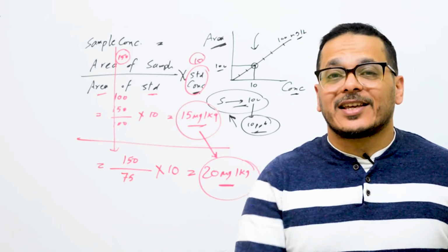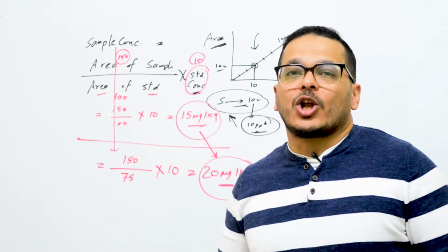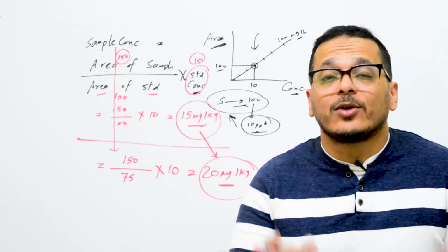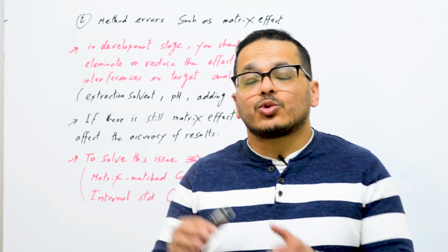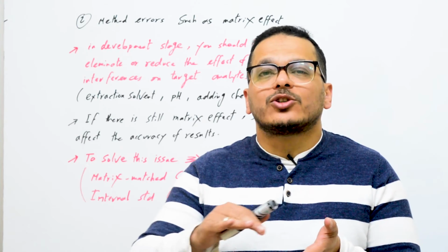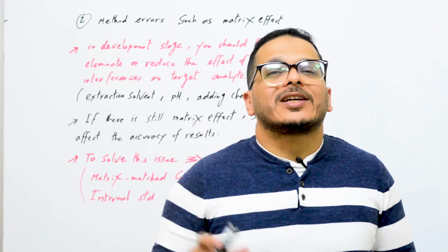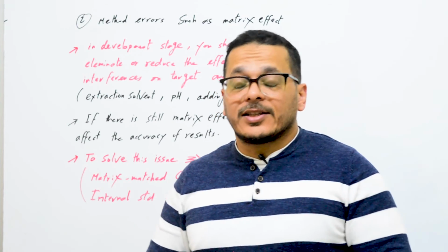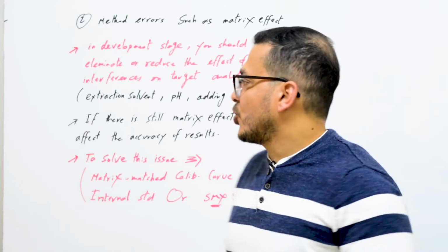That will happen every run. So this is a systematic error, because it will happen every run for all samples analyzed. So you should control this, and I will explain also how we can control these errors. For sure, in the previous example, to solve this systematic error due to calibration issues because of degraded standards, you should run quality control samples every run to know that there is an issue like this, and then you will buy new standards to fix the issue completely. But all of this will be explained after, in the next lectures, inshallah.